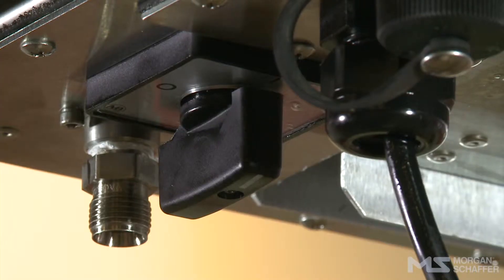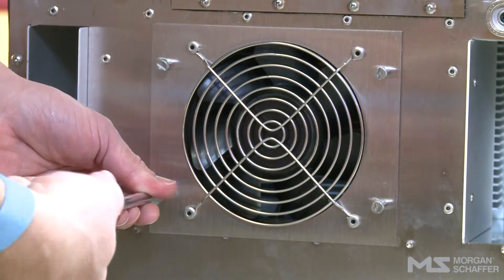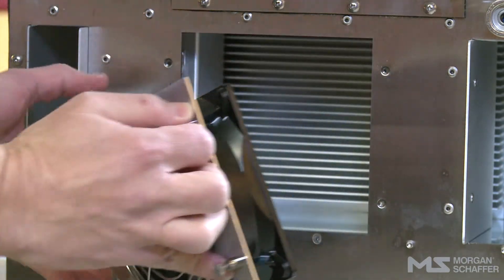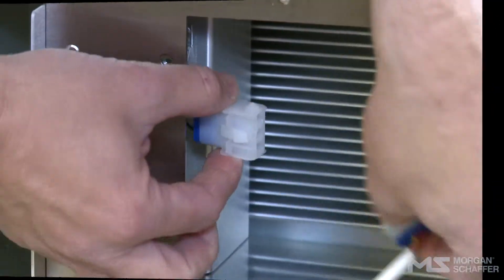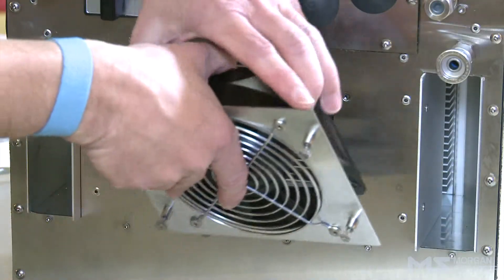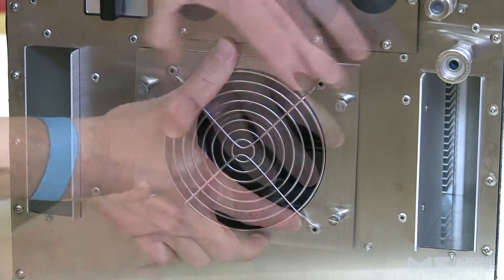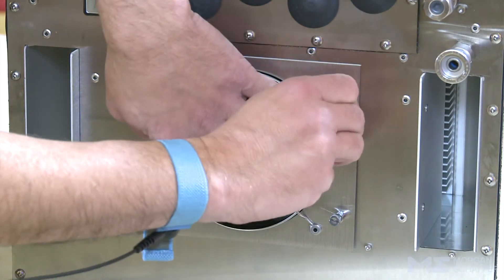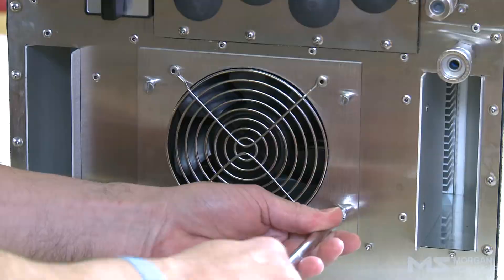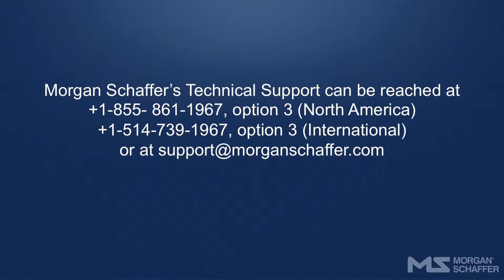Replace the fan. Turn off the Callisto and close its circuit breaker. Loosen the fan's 4 captive screws. If necessary, use a flat screwdriver to release the fan from the Callisto. Unplug the Callisto fan's connector. Set aside the old fan and prepare the new one. Connect the power supply for the new fan, ensuring that it is fully engaged and locked. Place the fan in position, taking care not to trap its wires. Manually tighten the fan's 4 screws, then complete the tightening using a flat screwdriver. Restart the Callisto. If the problem persists, please contact Morgan Schaffer for assistance.